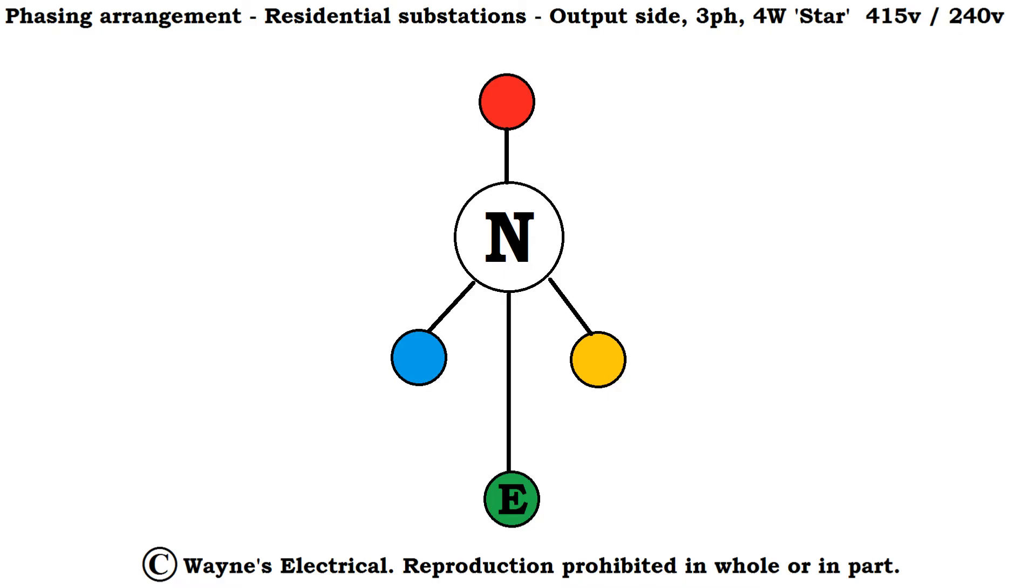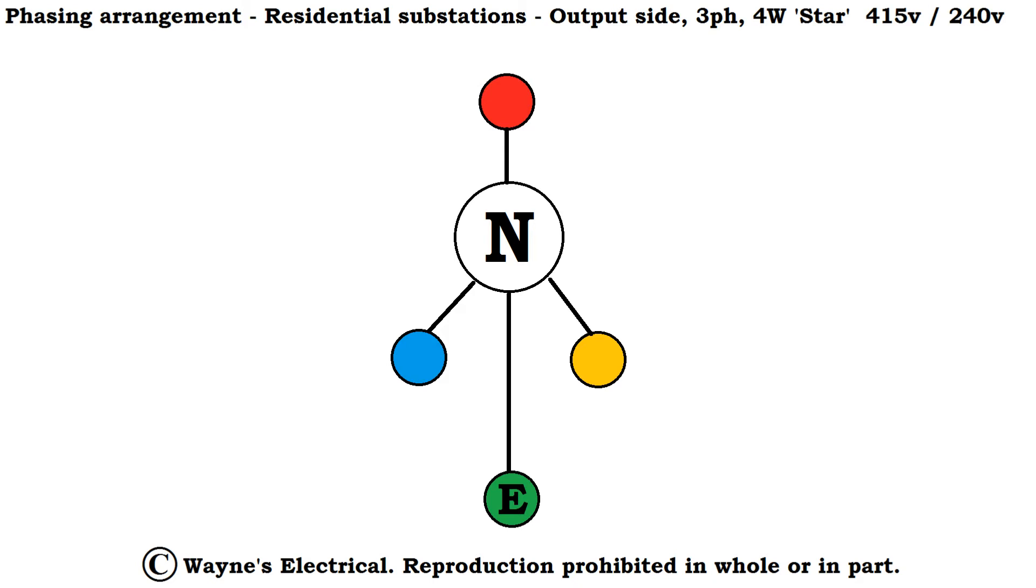Righty-o then, so we're into the screens. What we can see there on your screen then, full size, full HD size, it says phasing arrangement, residential substations, and we're looking at the output side of that, three phase four wire in star arrangements, which will give 415 slash 240 volts. Just to explain what's going on there, slap bang in the middle, we've got the big circle with the N in the middle of it, which symbolises neutral, normally referred to as the star points. The red, yellow and the blue, that's your three phases. And then that one right down the bottom there, which is green with the E in it, that's your earth connection, and that would normally be in the form of like a big earth electrode stuck in the ground, or it could be like a big copper mesh putting the ground underneath the substation.